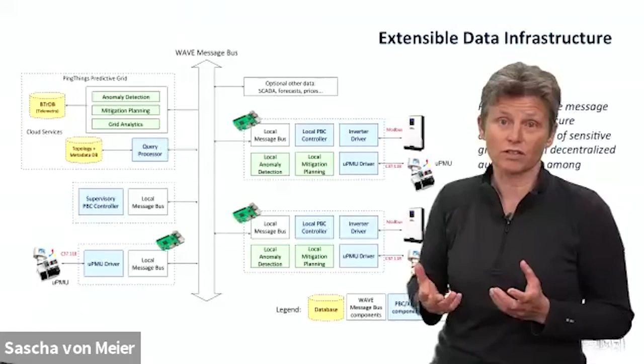This actually shows that we have Modbus talking directly to the devices, which is one common standard. For the PMUs, C37.118 is the regular standard. But I think the important thing to point out is that the message bus is really agnostic to the format. It can accommodate multiple different formats. Somebody can publish something in one format, and as long as whoever subscribes to it can read that, it works. So we're not limited per se. This is what we implemented here, but it could be other things.